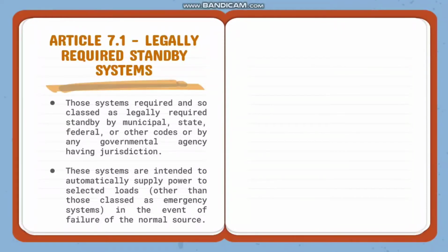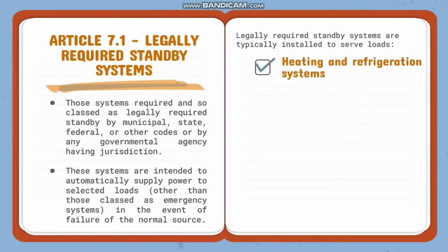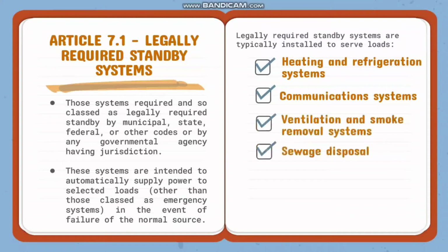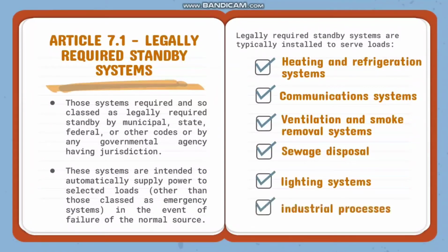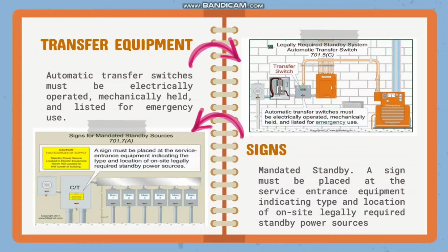So in other words, legally required standby systems are required by codes to illuminate or to power equipment that is not categorized as requiring emergency power, but whose failure could create hazards, hinder rescue, or hamper firefighting operations. So these systems are known as Level 2 or less critical systems. Legally required standby systems are typically installed to serve loads for heating and refrigeration systems, communication systems, ventilation and smoke removal systems, sewage disposal, lighting systems, and industrial processes. So the provision for transfer equipment and signs for legally required standby system is the same as the emergency system.